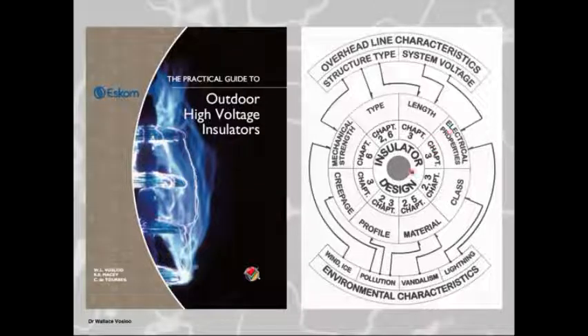Now, this insulator is not sitting in a lab which is pristine. This insulator is sitting out there in the environment, and the environment has a very large effect on the insulator. Actually, to be quite honest, the environment can reduce the insulation capabilities by 85, 90%. So you find that the environment can have a significant effect on insulator performance. So let's look at what environmental characteristics will influence this insulator design, and what parameters of the insulator's design are influenced by these different environments.